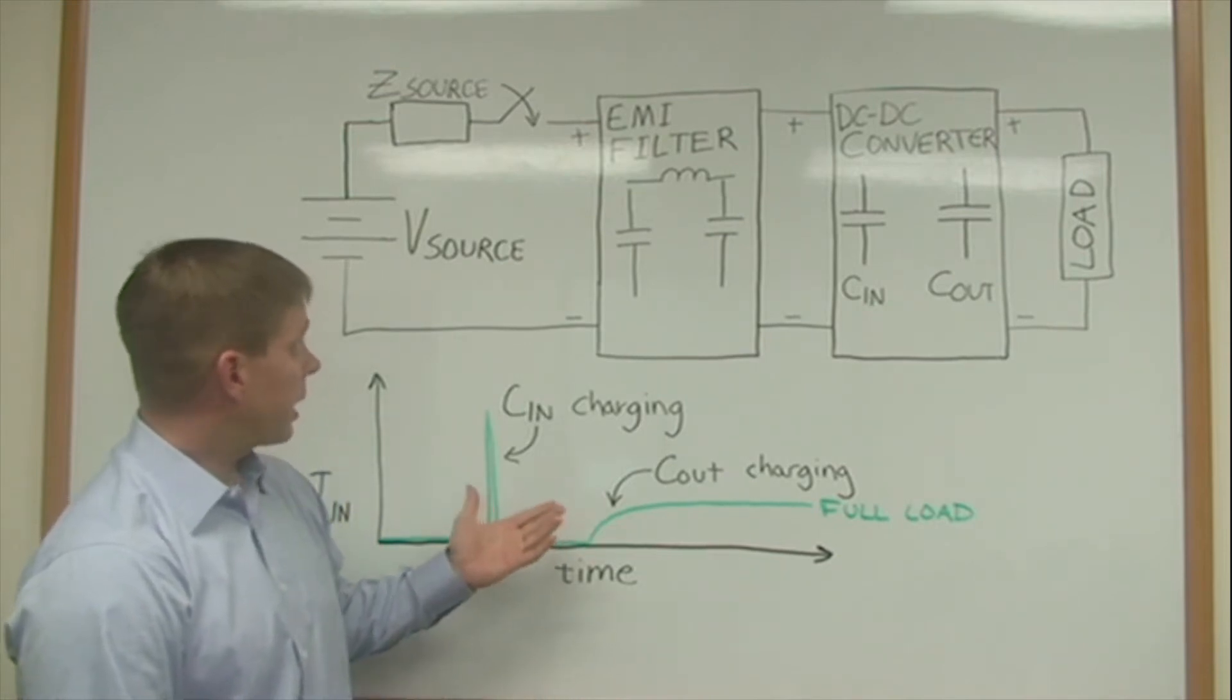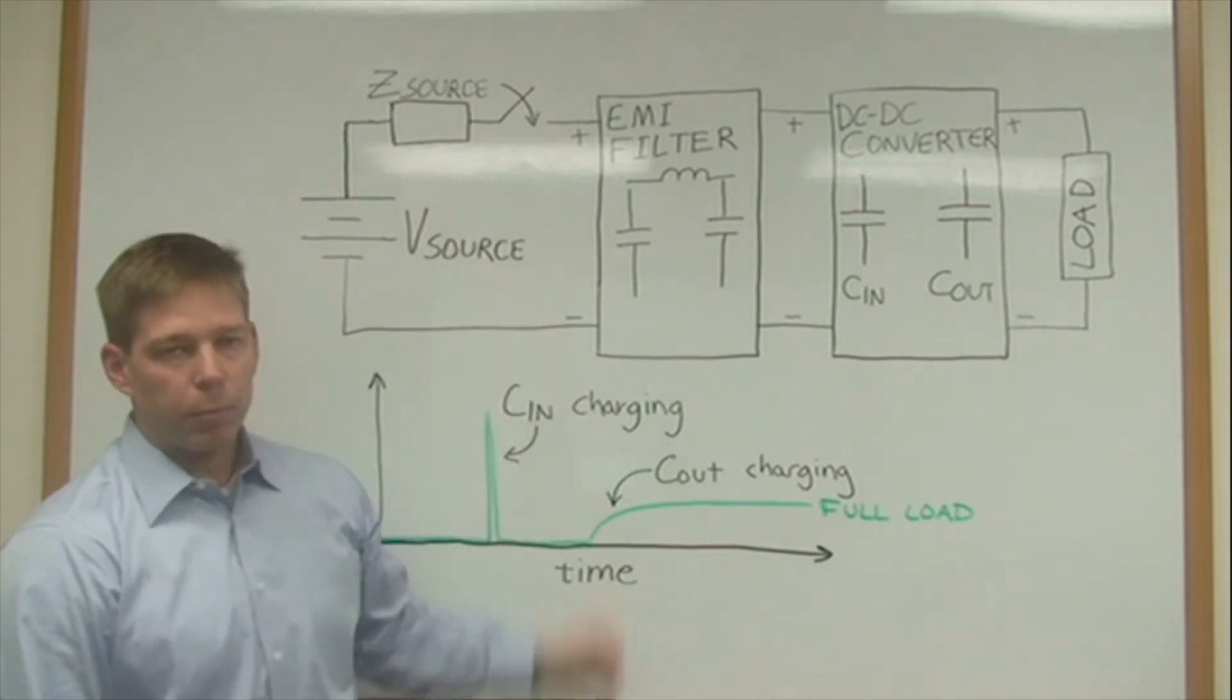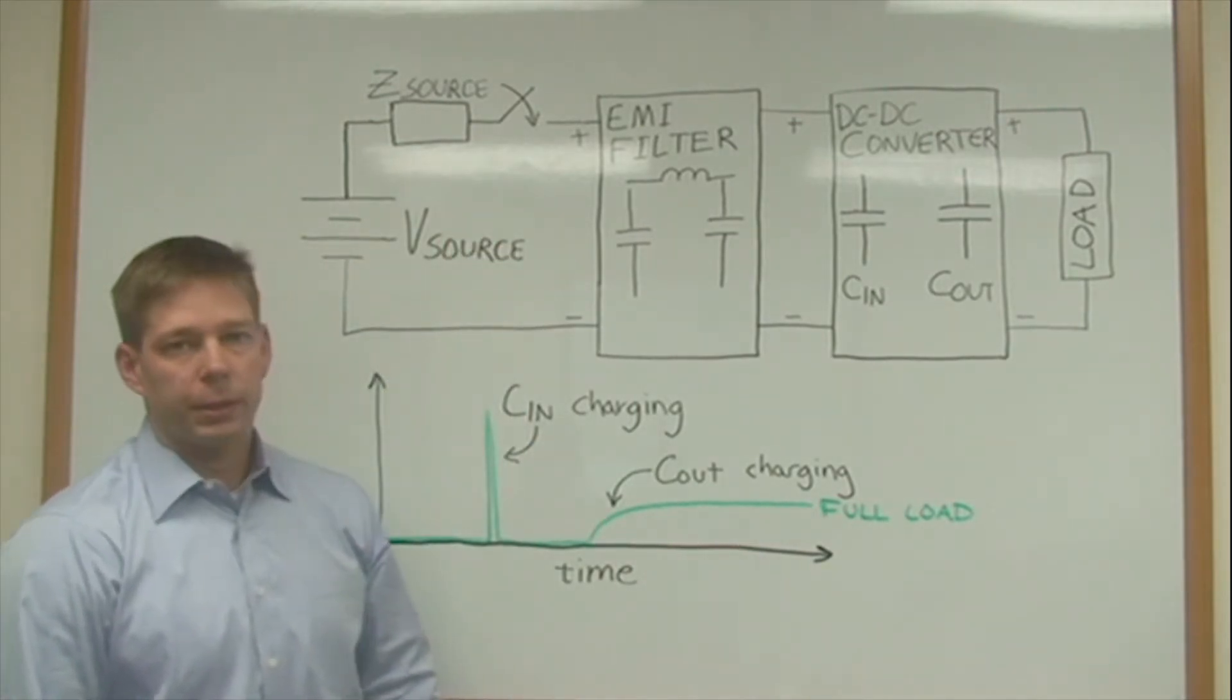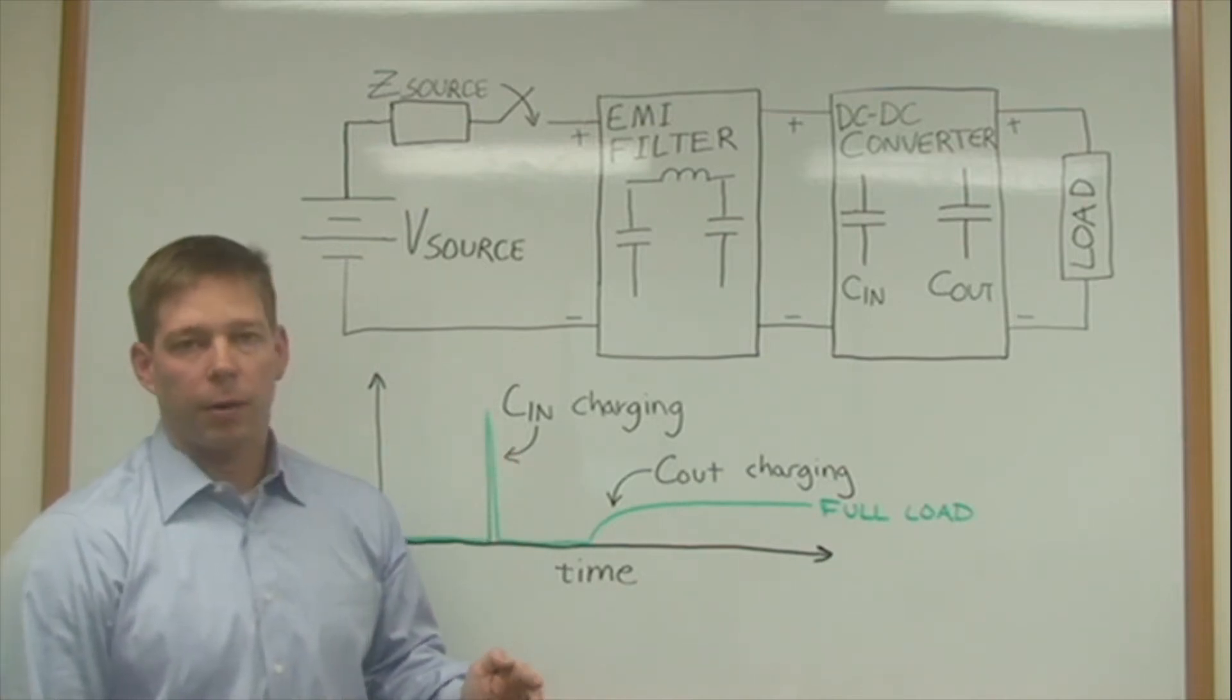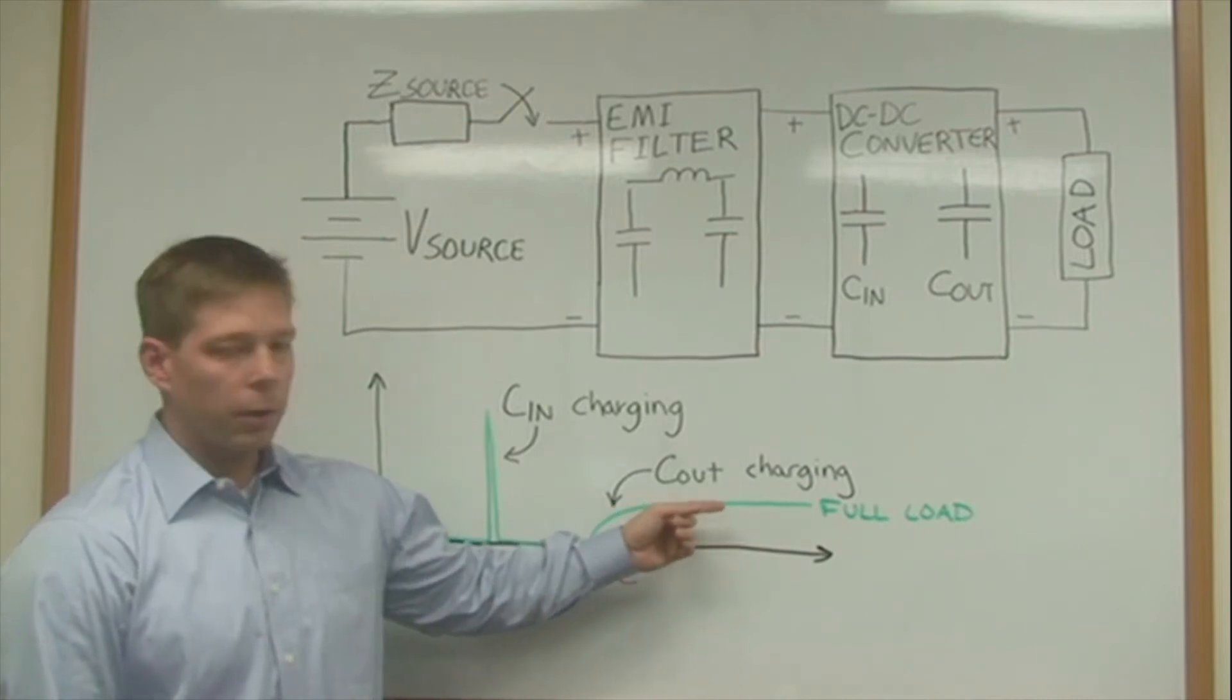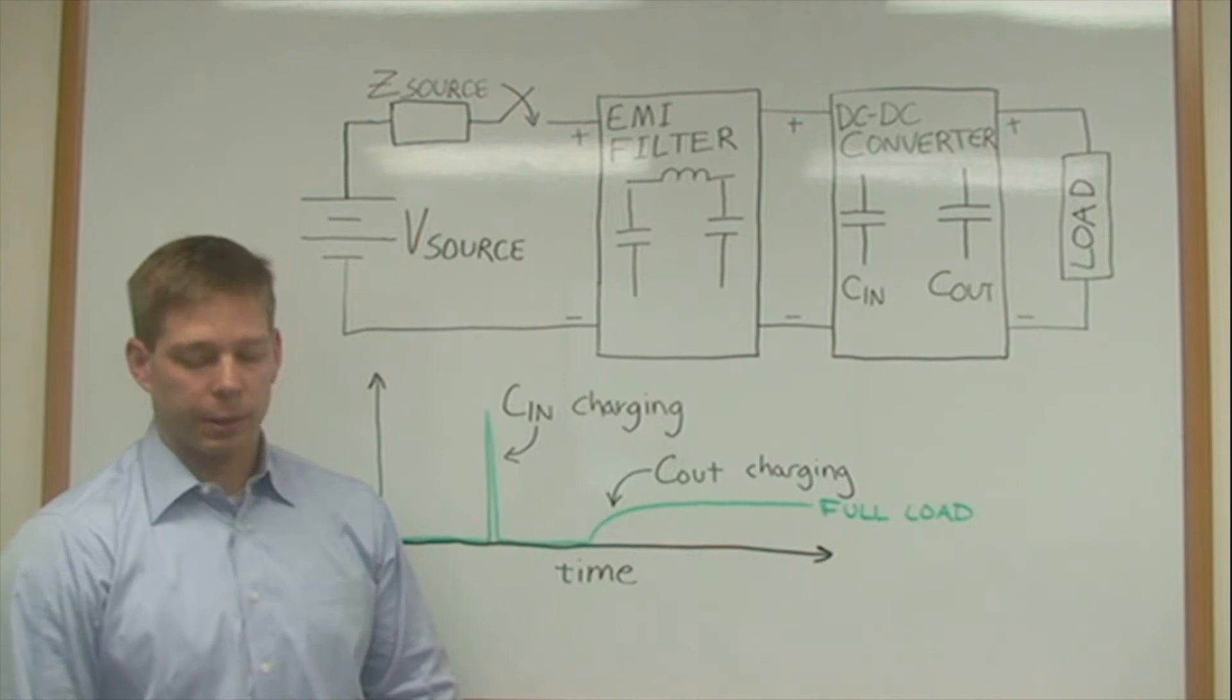So in those cases the fast dV/dt of the input voltage and the low source impedance causes this current to rise very rapidly, can reach peaks many times higher than the typical full load running current and that can cause EMI issues in a system.